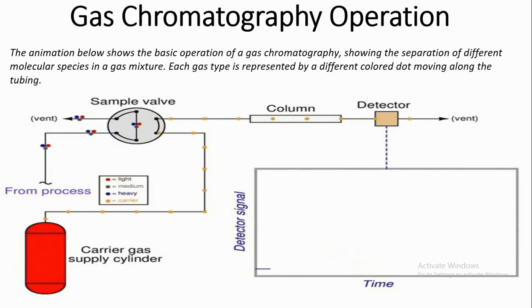These molecules move together at the same rate until they reach the column. There the light molecules (red) travel fastest, the medium molecules (green) travel slower, and the heavy molecules (blue) travel slowest. Thus the differing velocities within the chromatograph column perform the task of separation necessary to identify and measure each chemical component in the mixture.